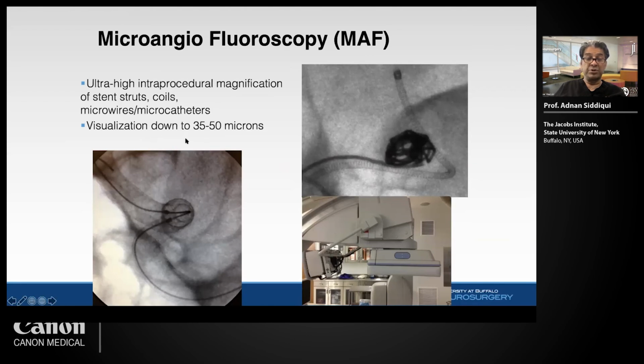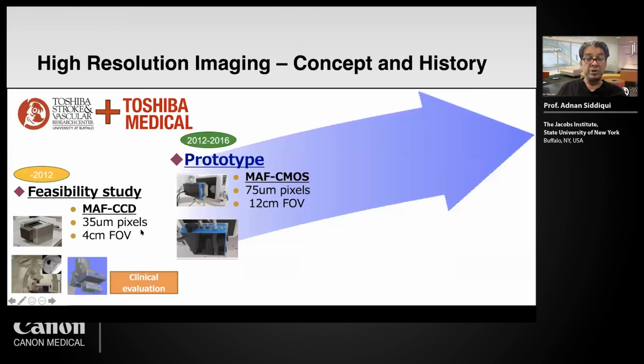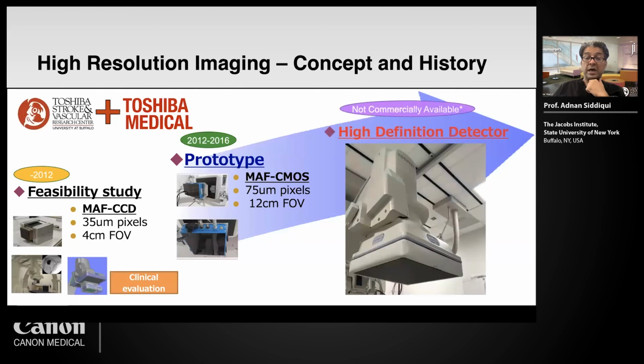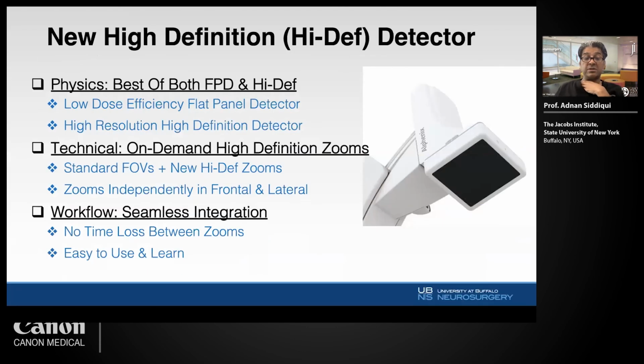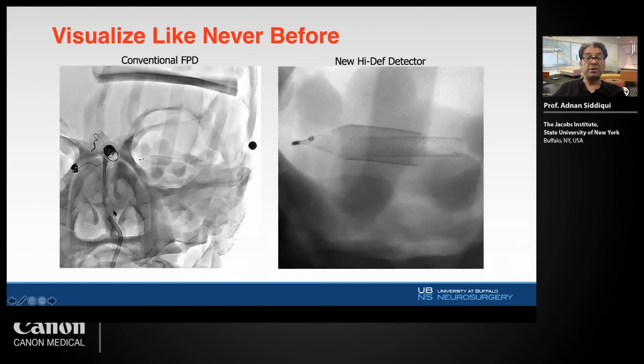He was able to bring this down to 35 micron resolution, where you could actually see the difference between one pipeline inside another pipeline. That was the kind of resolution you're getting. From that original study that we did in humans, the prototype that we have commercially available gives us about 70 micron resolution pixels, which is now available for clinical commercial use. And that's what I want to share with you: the value of this system is that there's a smooth transition between the standard flat panel detector, with standard FOVs, and the new high-def zooms. Really it's just a touch of a button as you mag up or down to zoom in from one to the other.